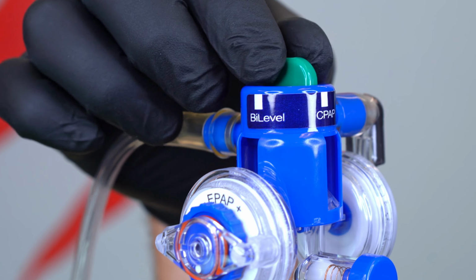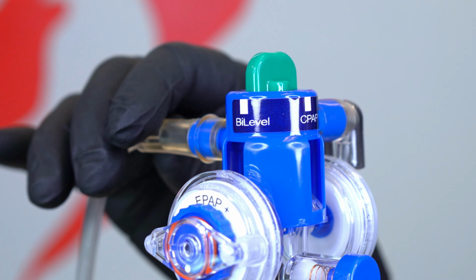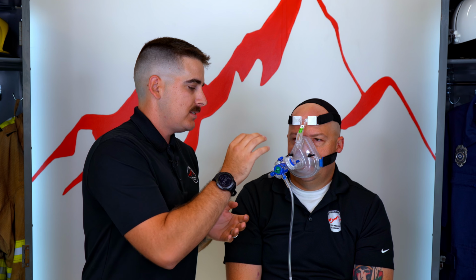And at this point, we can switch to that BiLevel mode. And to do that, we just turn this green dial here into BiLevel, okay? So now every time Chris takes a deep breath, that inspiratory positive airway pressure is going to be that max setting where that manometer reaches to. And so what I'm looking for is his inspiratory pressure, which is going to be 10 centimeters of water pressure. And then I can dial in my expiratory positive airway pressure. And so that's going to be still that CPAP mode, that kind of PEEP that Chris may need as well. And so the difference between that inspiratory positive airway pressure and that expiratory positive airway pressure is our pressure support. And that is what achieves that ventilation support that the BiLevel really helps with our patients.